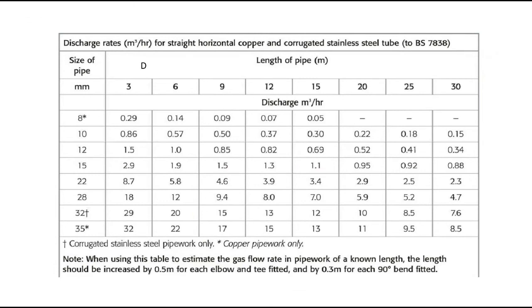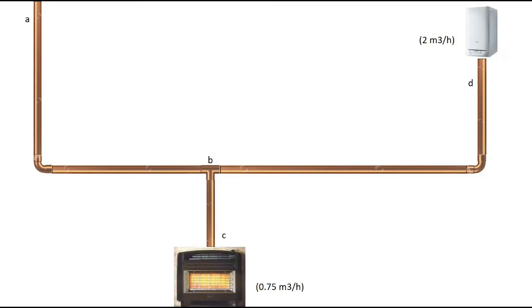Going to our table, we haven't got a seven-meter column, so we go to the next one up, which in this case is nine meters. We needed it to pass 0.75 meters cubed per hour, and the nearest value above that is 0.85 meters cubed per hour. We go back across the chart and it tells us our pipe size — in this case, for the pipe running from B to C, it needs to be 12 millimeters.